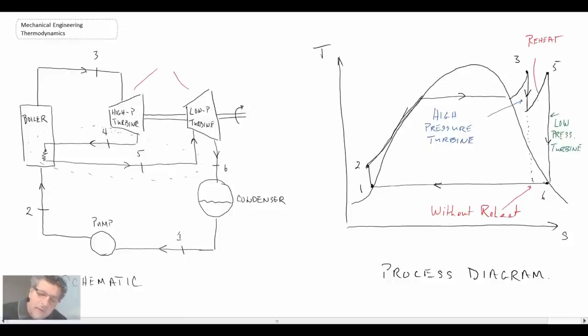And then in terms of the diagram, the changes are this reheat section here where we expand partially in our high pressure turbine. We reheat and then go back up to a high temperature and expand again. And the advantage of doing this, had we expanded directly from three down, we would have ended up in the two phase region. We would have had a lot of water droplets in our fluid coming out of the turbine.